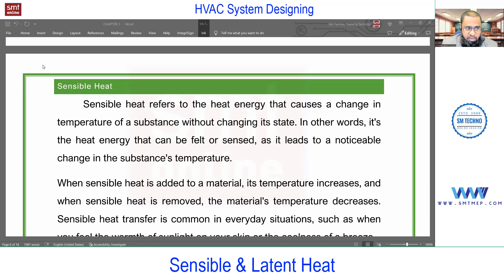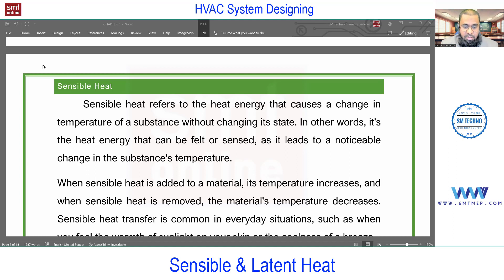Why sensible and latent heat is important — remember at the time of load calculation when we deal with different sources of heat gain or heat loss. Heat gain in summer and heat loss in winter. We find out the different sources of heat gain or heat loss. For example, in a cooling system for summer we calculate heat gain. Sources include heat gain through wall, through glass or window, through partition, floor, ceiling, ventilation, infiltration, people, lighting, appliances — we have a complete list.